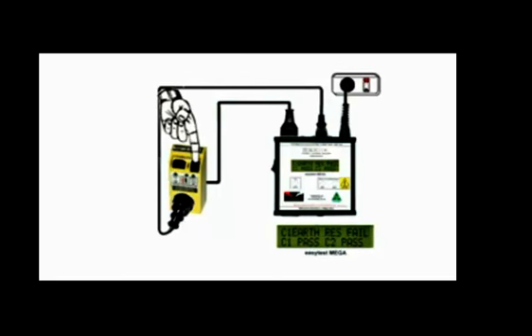So hit the reset button and check the test results. The lights indicate that the polarity is correct, the earth resistance is below 1 ohm, and the leakage current is below that set by the standard for Class 2 devices, so now we can test the safety switch. Press the self-test button and everything should go off. OK, so that works. Now it's time to reset and let the EASYTEST Mega put that unbalanced load on it and measure the switch times.